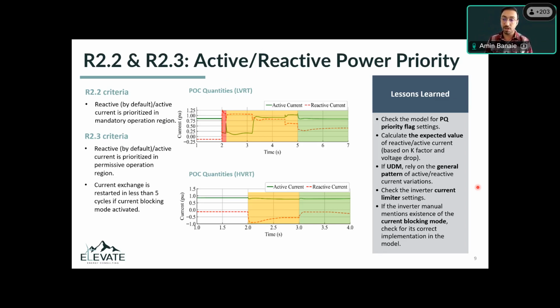And for these 2 requirements, we calculate active and reactive current at the inverter terminal and focus on those to investigate if the inverters are operating in Q or P priority modes. Analyzing and understanding if an inverter is correctly implementing active or reactive current priority is very complex. So again, we went to IEEE 2800 because they have a very clear definition of what is active or reactive current priority mode. As an example, for reactive current priority mode, that standard says that reactive current should have access to the entire current capacity of the IBR and take whatever it wants, and then anything remaining is going to go to active current. To identify this, you can do it in different ways, depending on whether you have a generic model or a UDM. For generic models, I would say go and check for the PQ flag in the settings of the model.